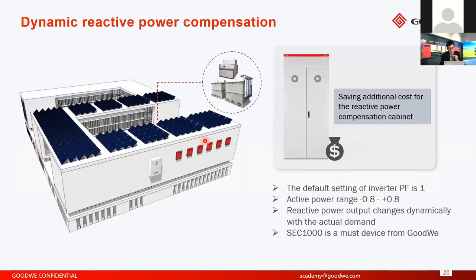And here is dynamic reactive power compensation. As you know, if you install a PV system on, for example, a factory, the PF will drop a lot. For example, from 0.9 to 0.8 or maybe even to 0.7. So the owner of the factory will ask you to do reactive power compensation for his factory, because if the PF drops a lot, that's a problem for him.